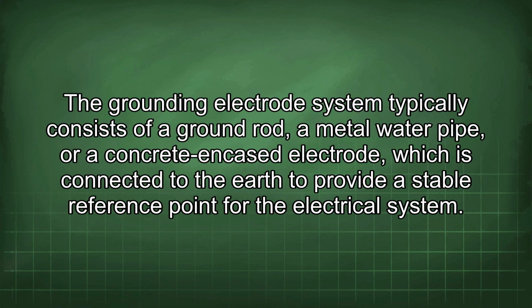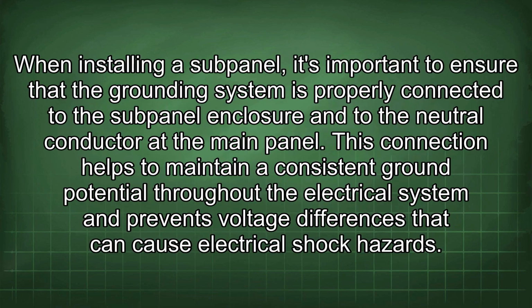The grounding electrode system typically consists of a ground rod, a metal water pipe, or a concrete encased electrode, which is connected to the earth to provide a stable reference point for the electrical system. When installing a subpanel, it's important to ensure that the grounding system is properly connected to the subpanel enclosure and to the neutral conductor at the main panel.